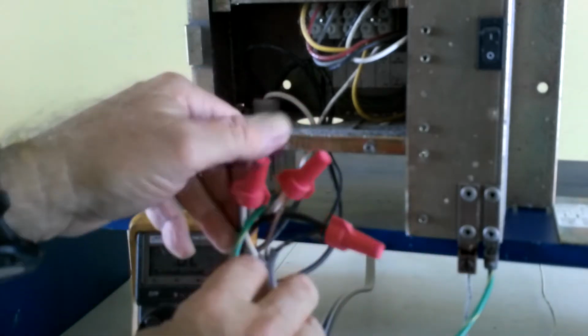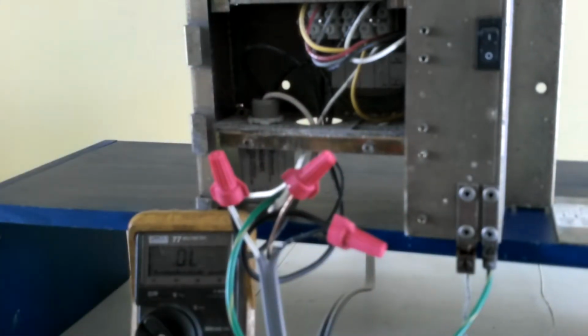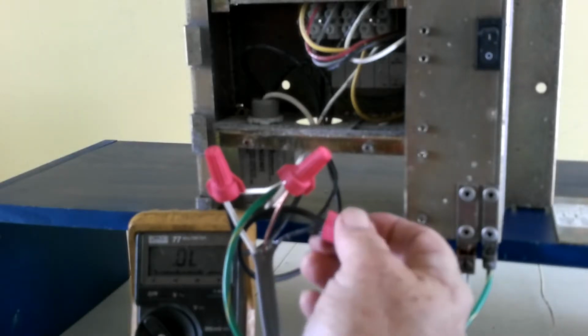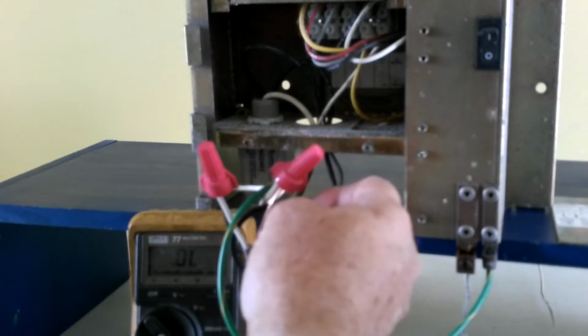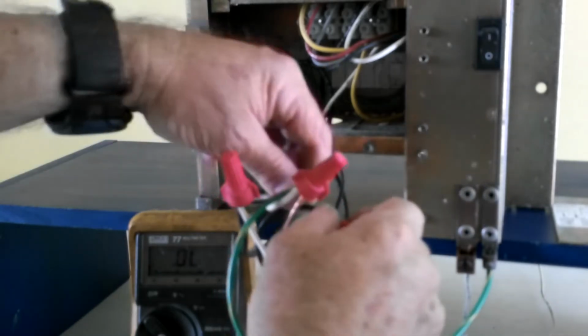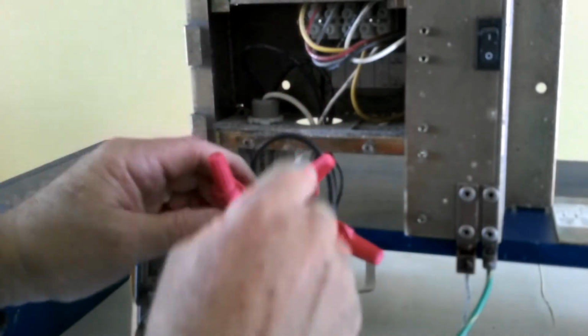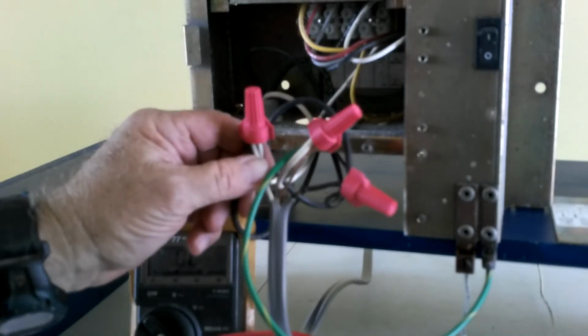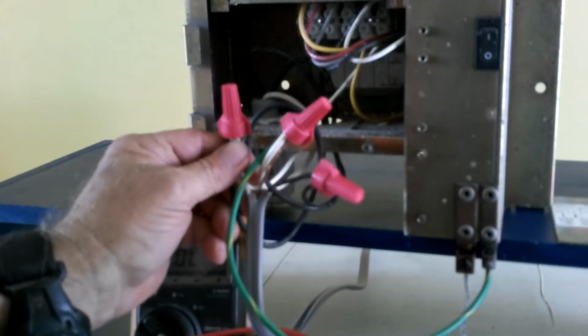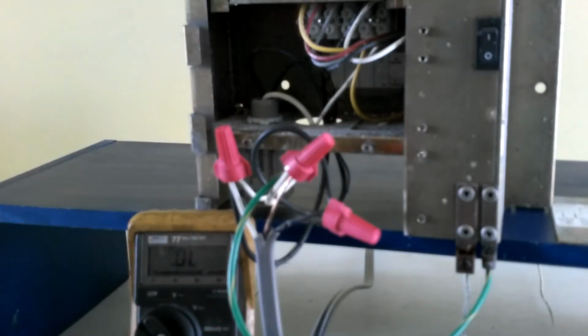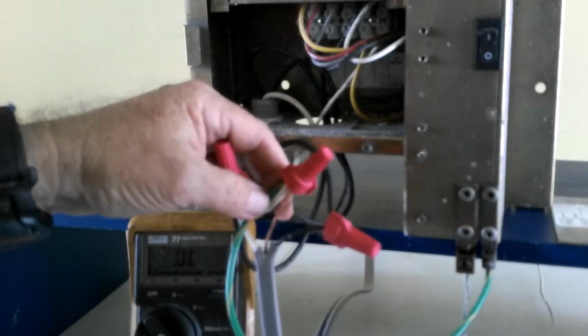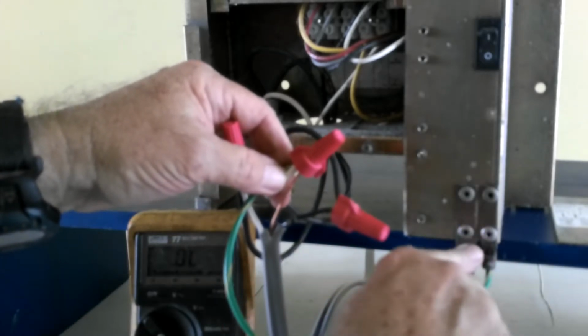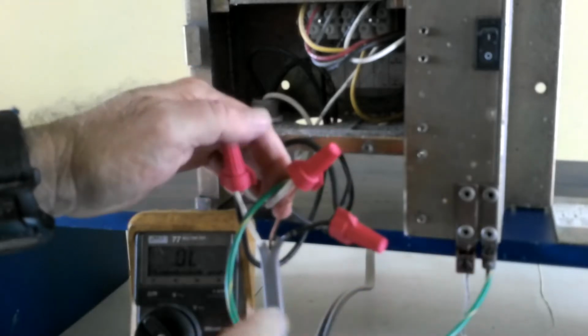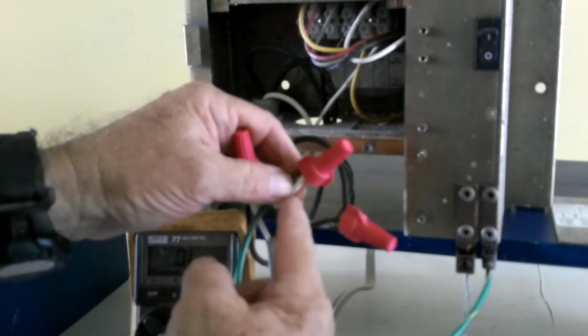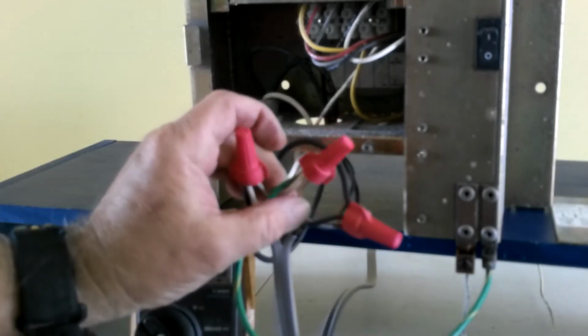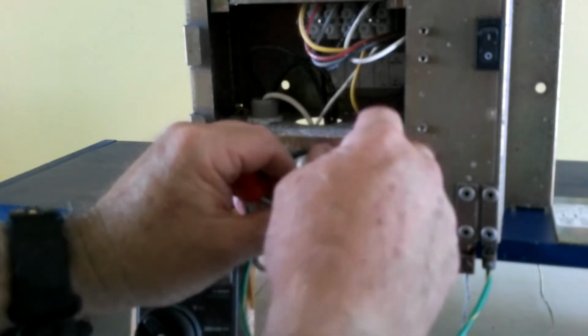So now that we have those connections made, it's ready to operate. So we've now connected the black AC hot lead and the hot lead going to the transformer together with one of the black wires from the surge arrestor. We've connected the neutral, typically white wire from the power source and coming from the transformer to the other black wire of the surge arrestor. And the white wire from the surge arrestor is now connected to the ground rod, earth ground connection here, as well as the bare copper ground wire that runs with the power wire that goes back to a ground connection at the power source.